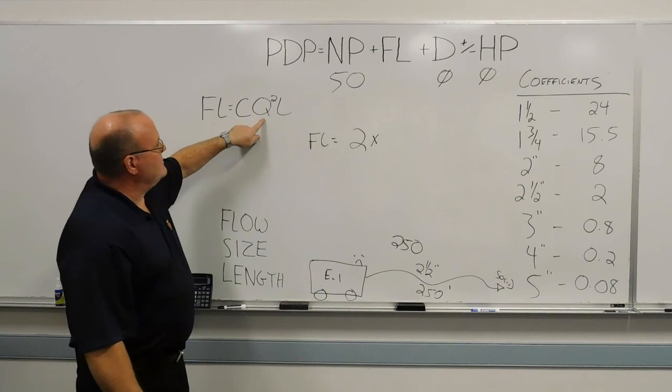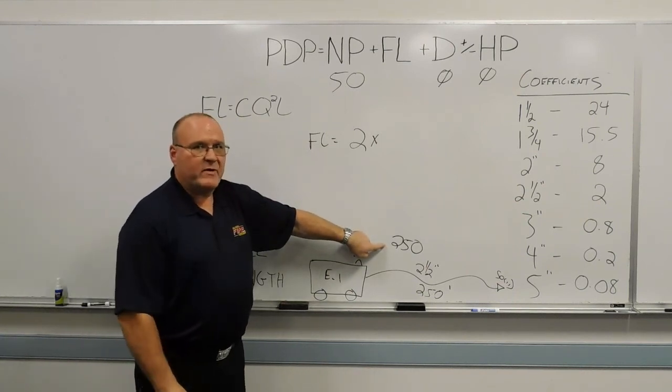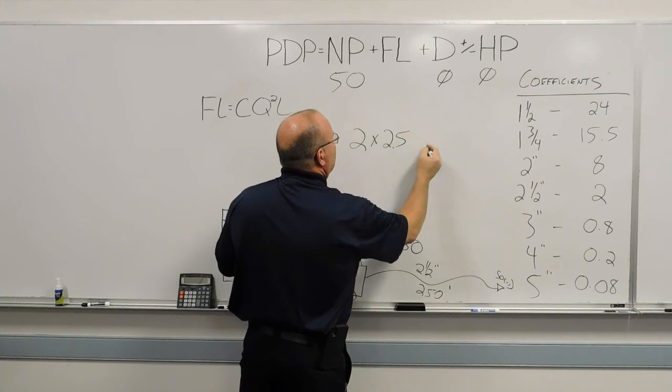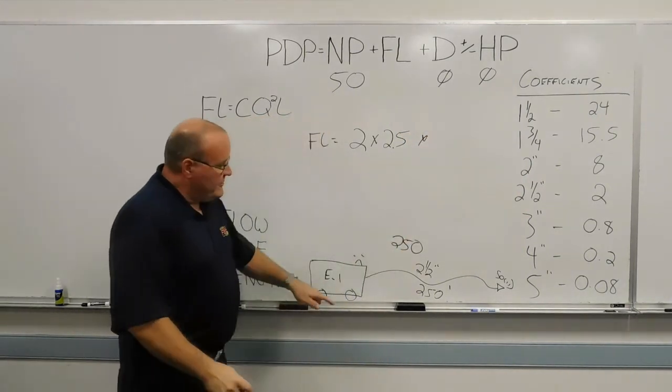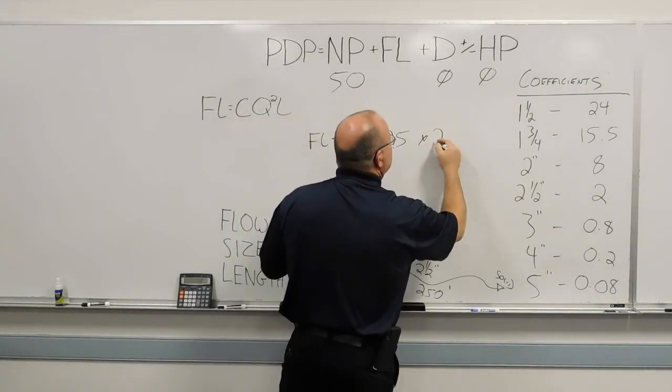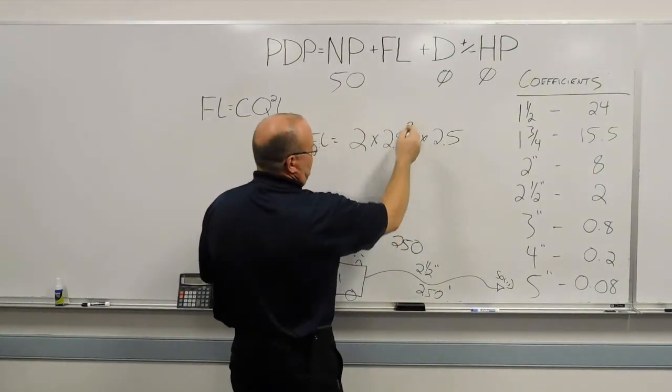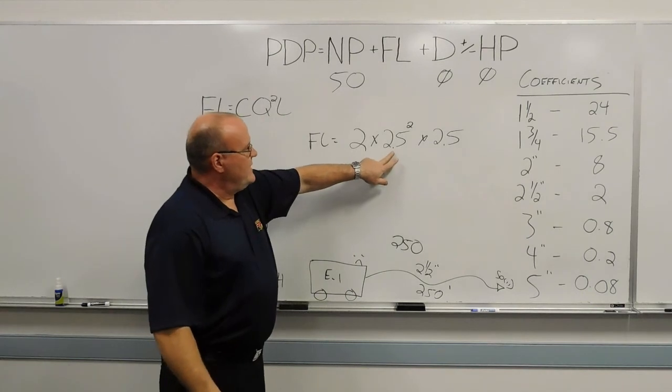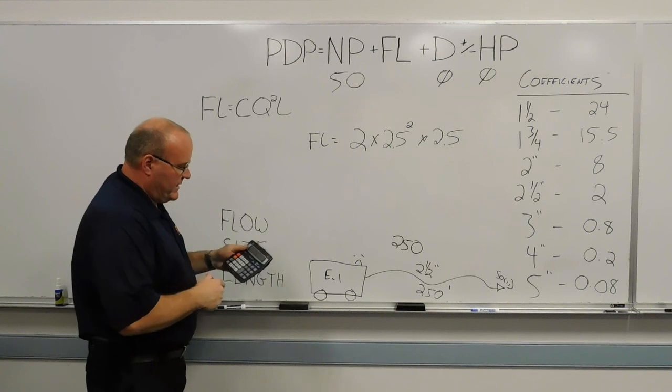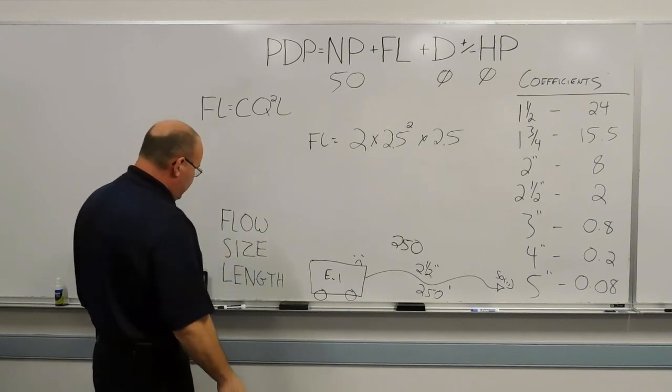The Q squared part, quantity squared in gallon per minute, is 250 gallons a minute. Divide that by 100 to get 2.5. And then the length, 250 feet, also divided by 100, 2.5. So there, the first step in the middle, we're going to square that 2.5. I'll get my handy calculator out here. And we're going to end up with 6.25.